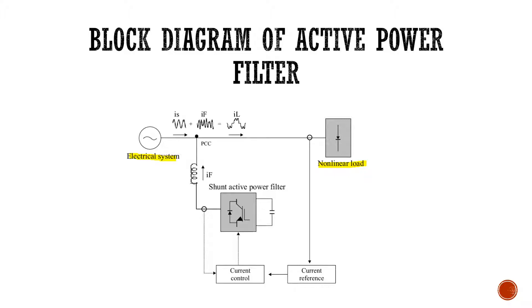The current reference is given to a current control unit. Most commonly, we are using a PWM control or a hysteresis current control for this type. This current control unit gives the pulse that is required for the shunt active power filter, so that the shunt active power filter feeds back the filter current to the point of common coupling. This filter current IF compensates the harmonic present in the grid and makes the harmonic levels in the grid system under control, so that a perfect sinusoidal wave with maximum power quality is present in the system with near-zero harmonics. This is the working principle of a shunt active power filter.